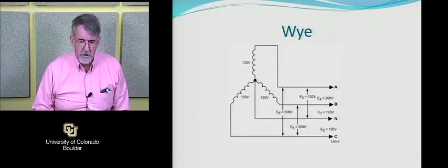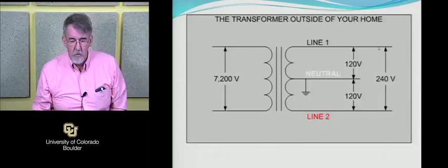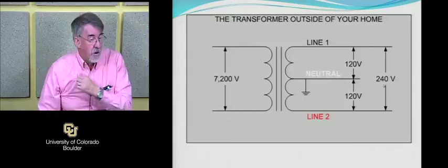So the transformer outside your house comes in with single phase, a few thousand volts. It goes into the secondary side, which really has two windings, or one winding with a connection right at the center coming out. So you bring out a neutral connection, and you can take line 1 to neutral at 120 volts, or line 2 to neutral at 120 volts. If you look in your breaker box there are two rows of breakers, and you try to get those balanced so line 1 and line 2 have equal loads. But if you go across line 1 to line 2, you get 240 volts, which is where your electric dryer or oven would hook up.